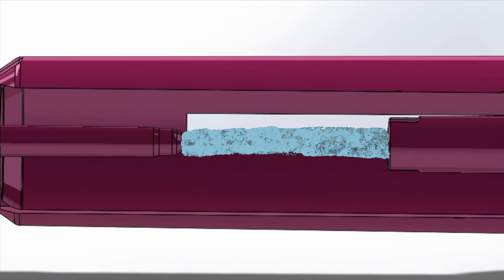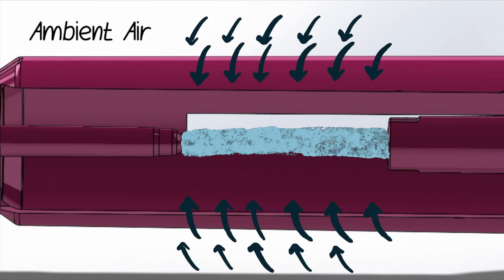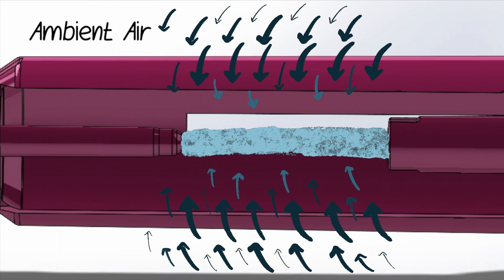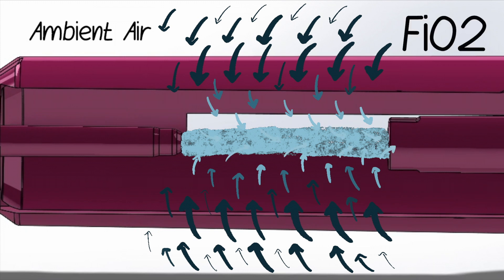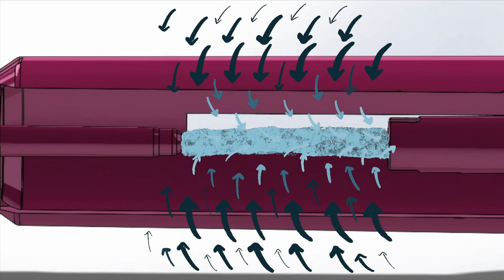The low pressure jet pulls ambient air into the blender through holes on its side, just like the paper sheets are pulled together when air is blown between them. As ambient air enters the blender it mixes with the oxygen jet. The amount of ambient air pulled in determines the FiO2 concentration. This air mixture is then captured at the exit of the blender and delivered to the patient.